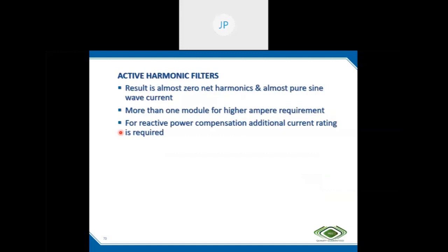With a passive filter, the same filter can be used for reactive power compensation and harmonic mitigation. Here, if 100 amps mitigation is required, we need a 100 amps active harmonic filter. If we need 100 amps of reactive power compensation current, then another 100 amps is required. So this is highly costly. This is a costly solution.